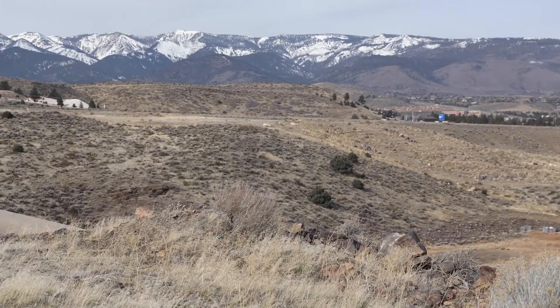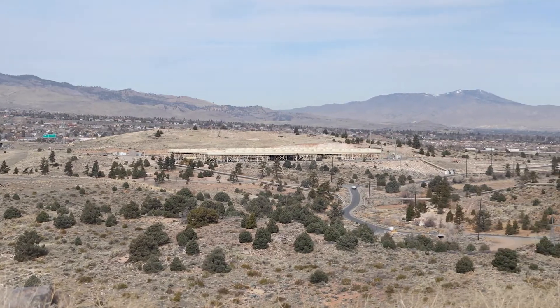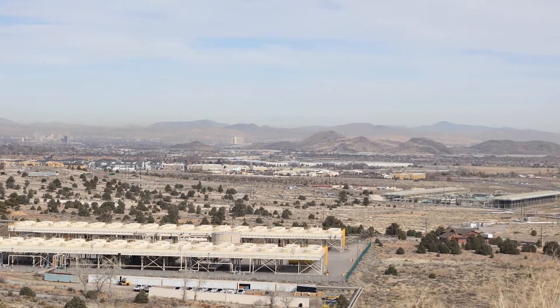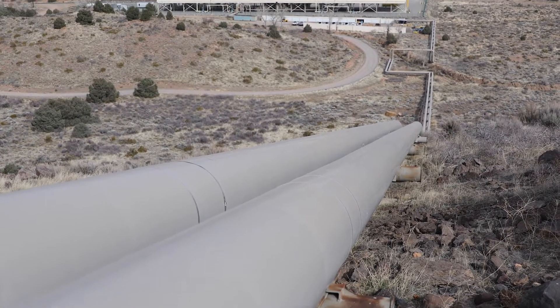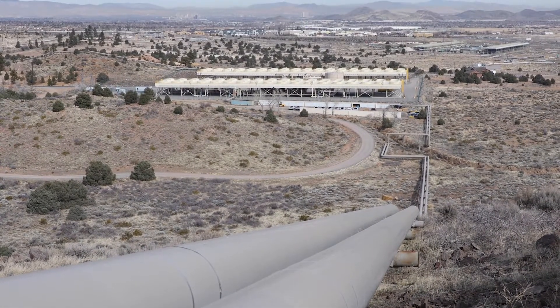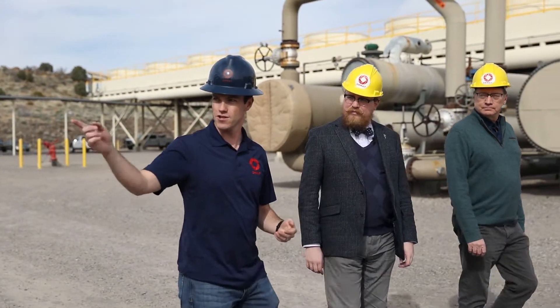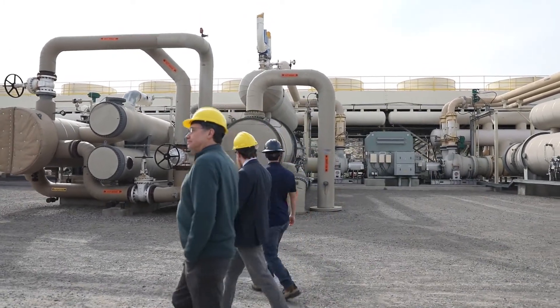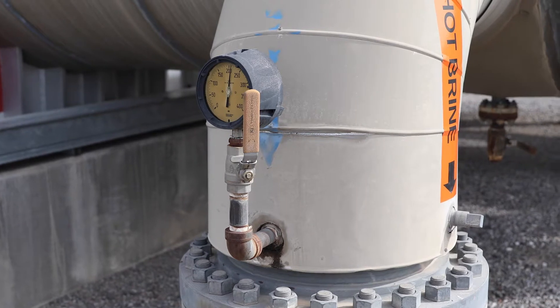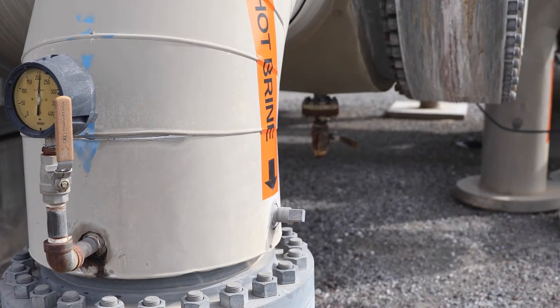What exactly is the Steamboat Geothermal Complex? The Steamboat Geothermal Complex is made up of six different power plants covering from close to the highway all the way back down to the top of the hill. Those six power plants generate 65 megawatts of electricity on average, and there are 25 production wells that feed each of those plants. We pump the geothermal fluid, which is very hot, through a power plant, and we boil a working fluid — pentane — which is part of the binary geothermal generation process. This is an efficient way to extract the heat and re-inject everything back into the ground so it can recover heat from the earth's rocks and return to the wells again.